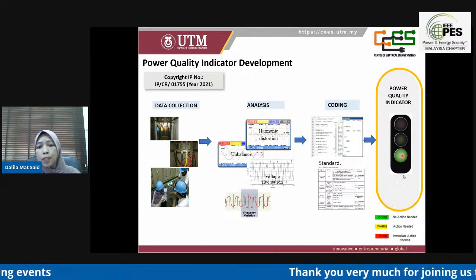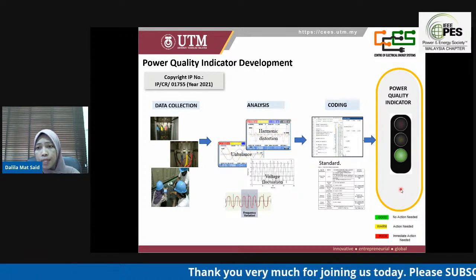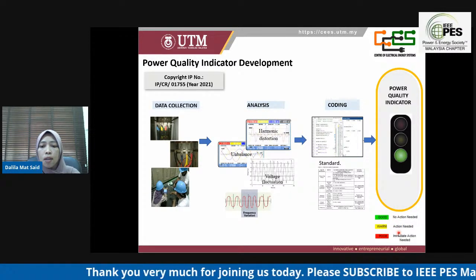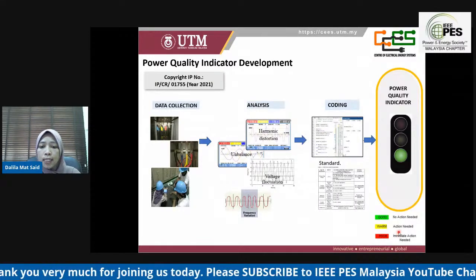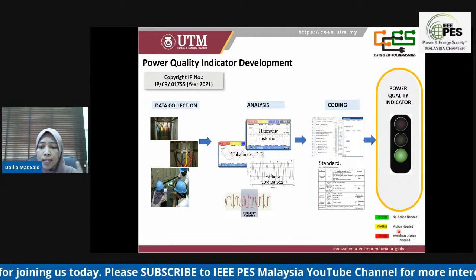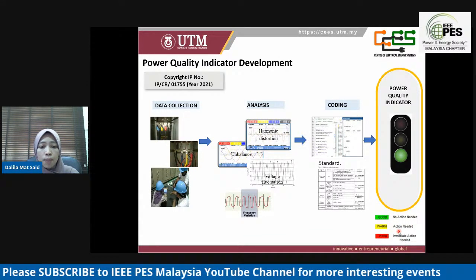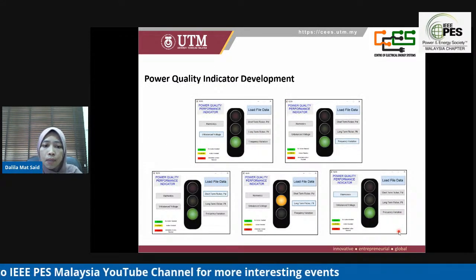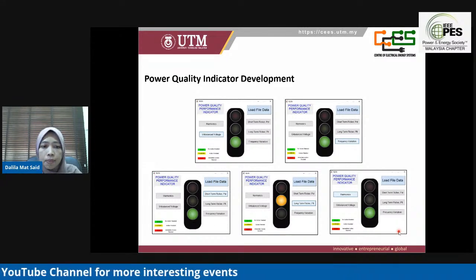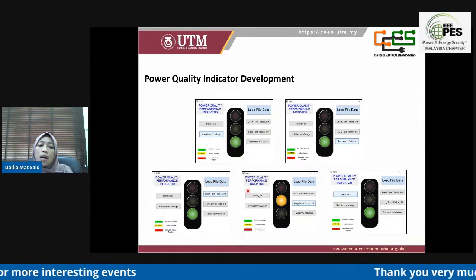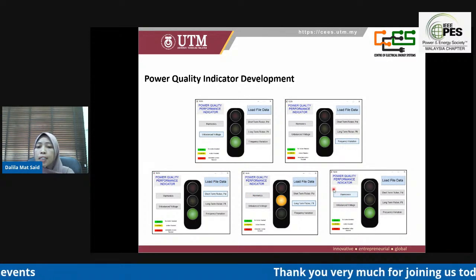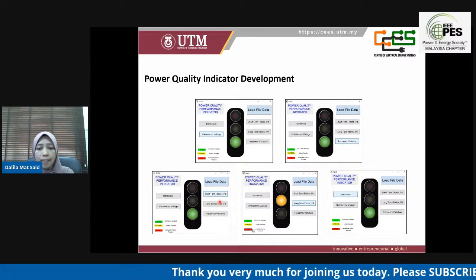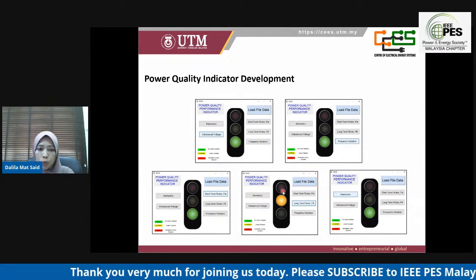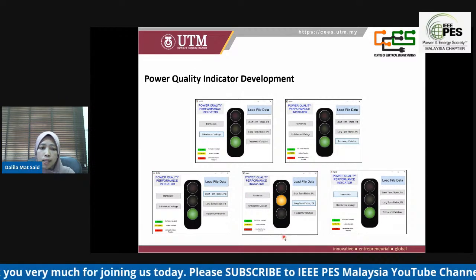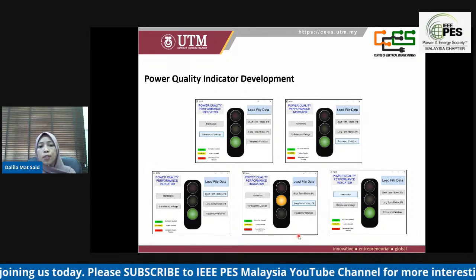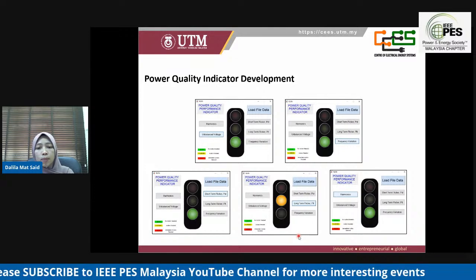This indicator is based on color coding: green, yellow, or red. Green indicates good quality, yellow indicates action needed, and red refers to poor quality. I will show an example of the indicator. This is an example of output run from the selected substation, where all the parameters are green except one PLT value, which indicates a warning. This is the yellow color.